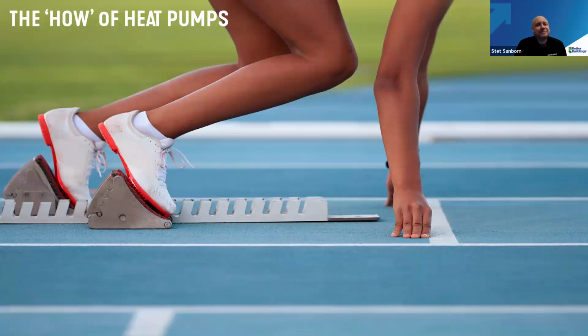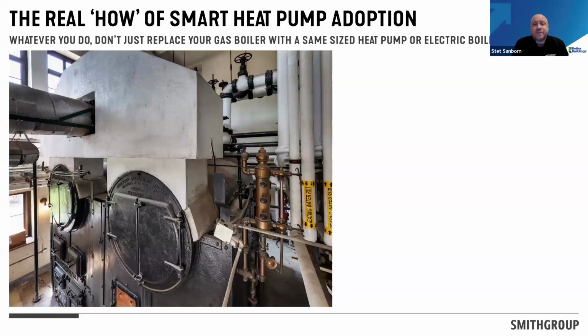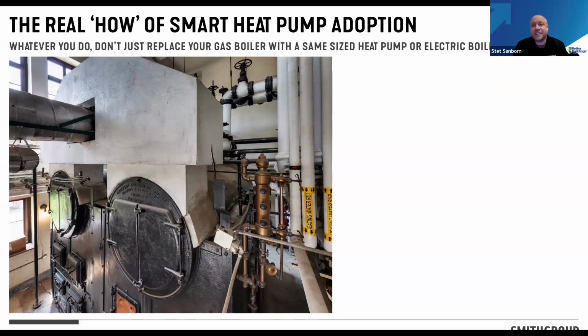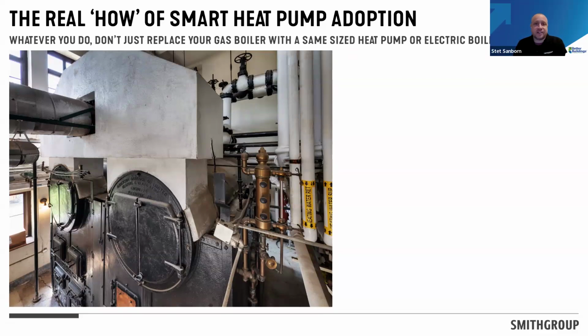The worst thing you could possibly do for your project is walk down into your boiler room, look at the nameplate size and capacity of your boiler, and just pick a heat pump that matches it. I can guarantee your project will be over budget. You're likely going to run into electrical infrastructure upgrade constraints that blow your budget out of the water, and you'll also likely end up with really poor performance.